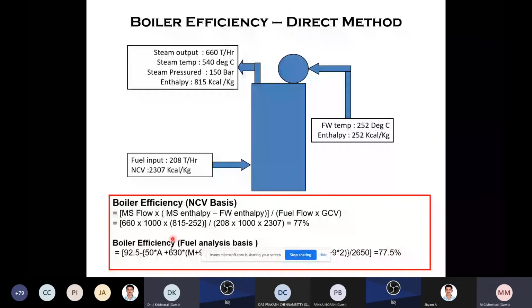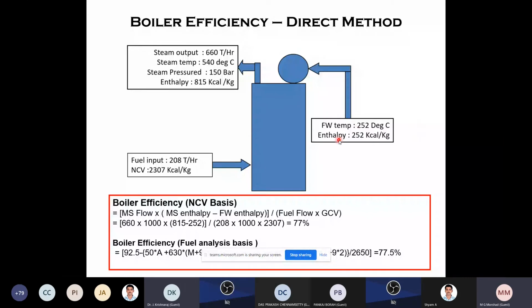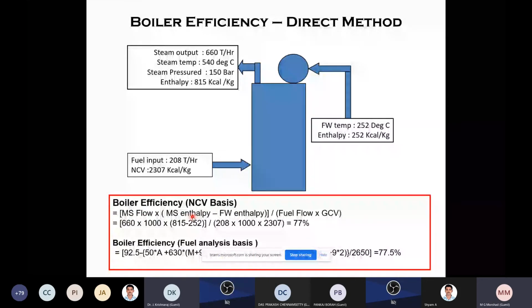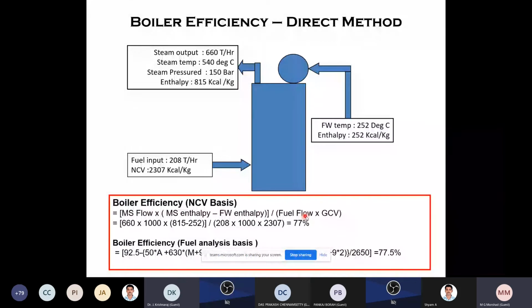Then for the direct method, we use two approaches: the GCV basis and the fuel analysis basis. On the GCV basis, we take the fuel going in and the input feed water, so the feed water temperature and enthalpy of the feed water. So boiler efficiency is the main steam flow times the main steam enthalpy minus feed water enthalpy, divided by the fuel flow times the GCV. I can very easily calculate it within 5 minutes, and get 77% boiler efficiency. So this is the direct method.